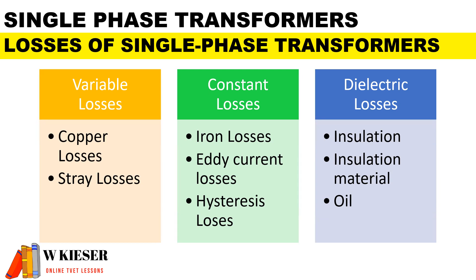For constant losses due to the iron core, we have two types of iron losses: eddy current losses and hysteresis losses. Eddy current losses create unwanted heat and energy loss, and in order to reduce the effects of eddy current losses, we use laminated steel sheets.